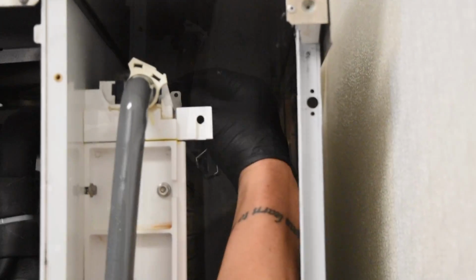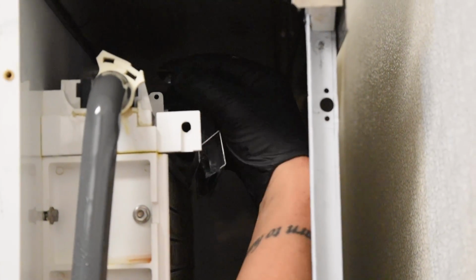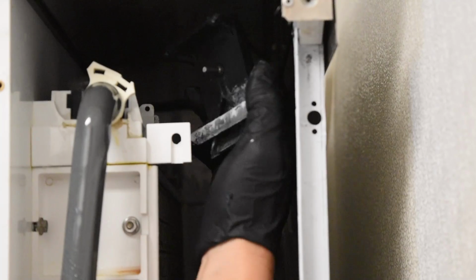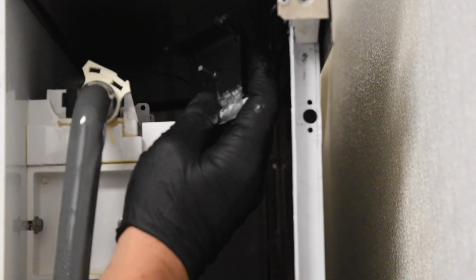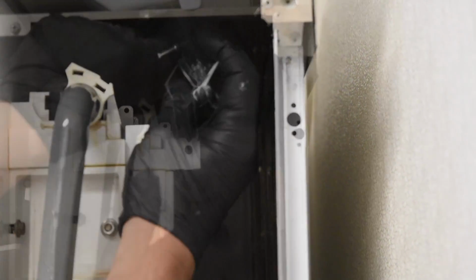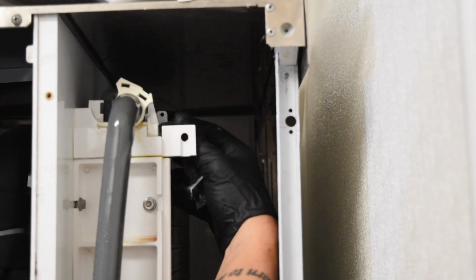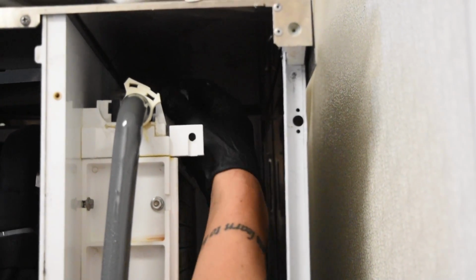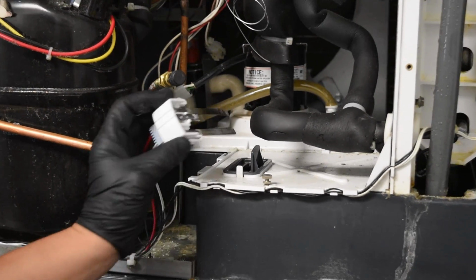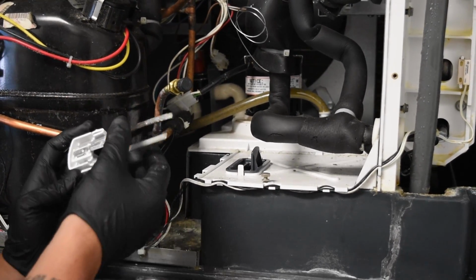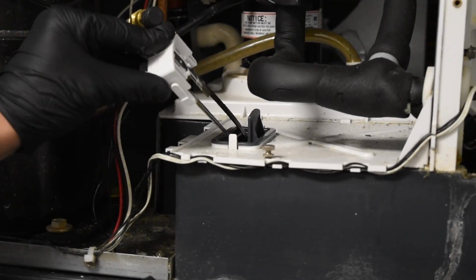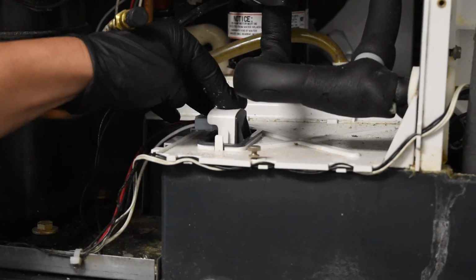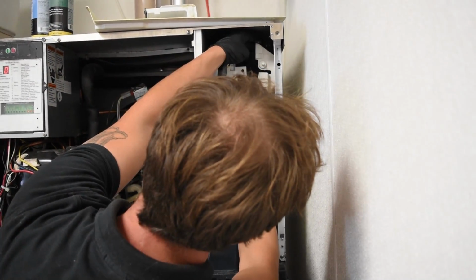Once you have removed the ice curtain, gently detach your ice thickness probe, being careful not to pull on it as it is attached with a wire not meant to come apart. Clean the scale off the probe with a rag or green abrasive pad and put it back in place. Pull your water level probe out and clean off the scale with the same rag or green abrasive pad. Put the probe back in place. You are now ready to add the descaling chemical.